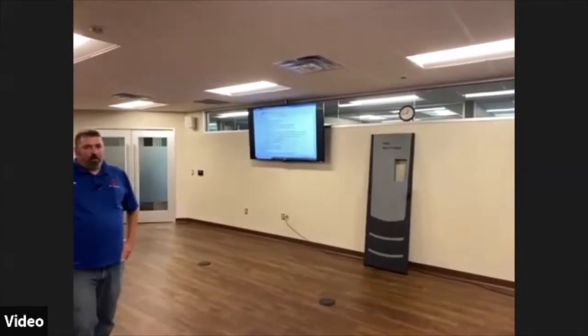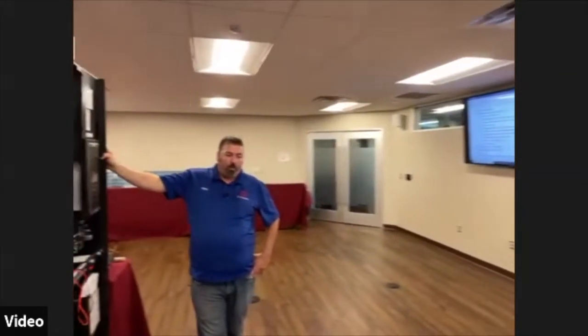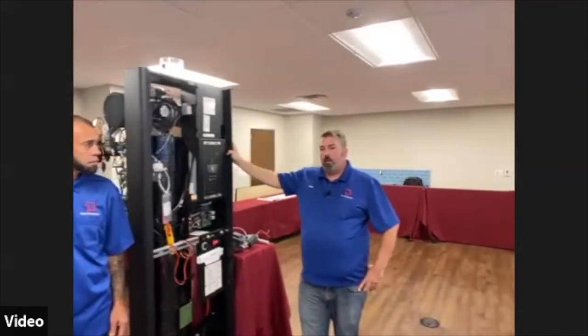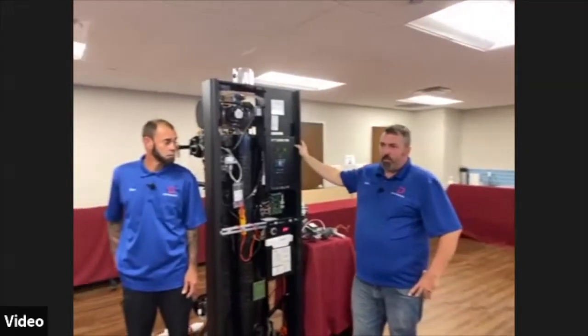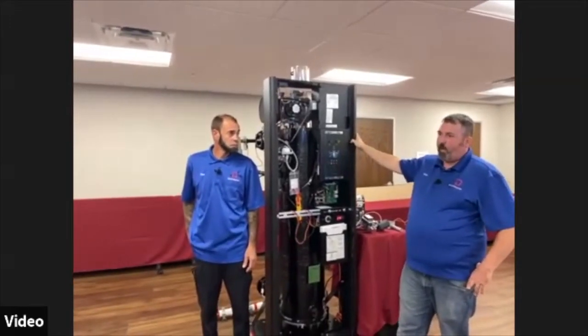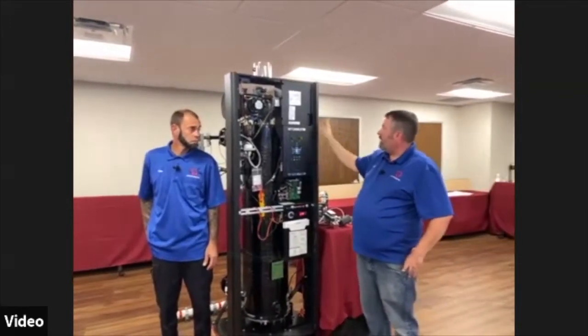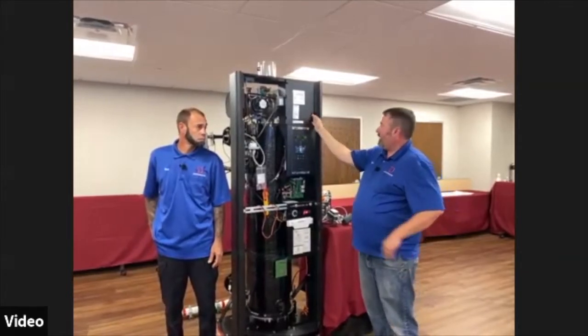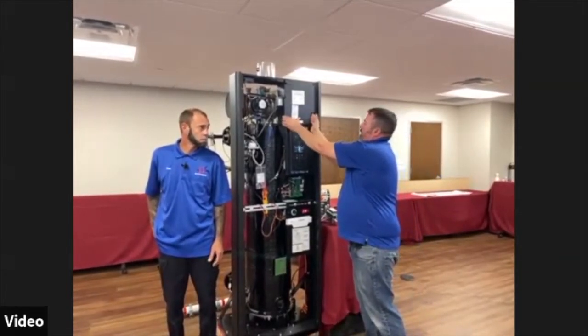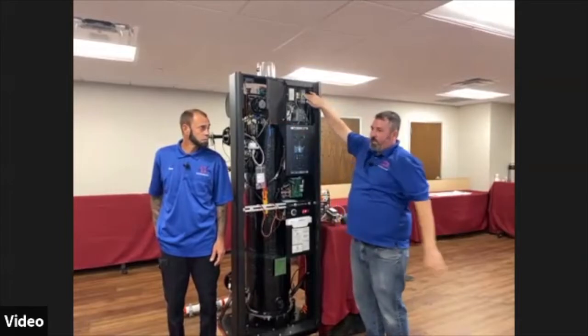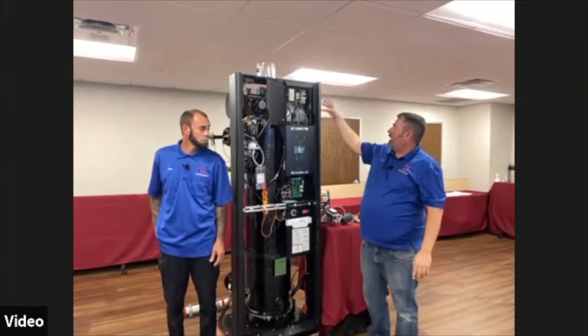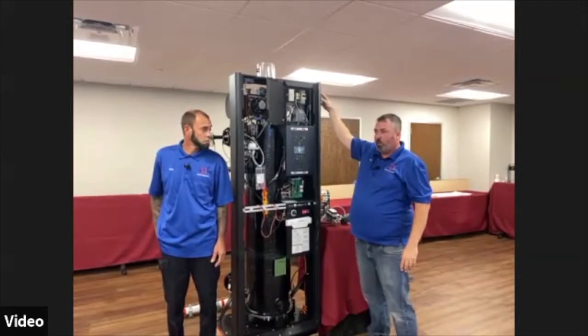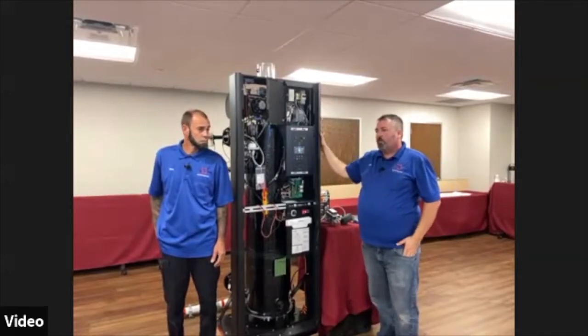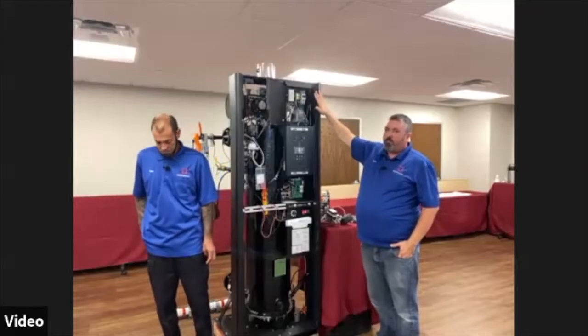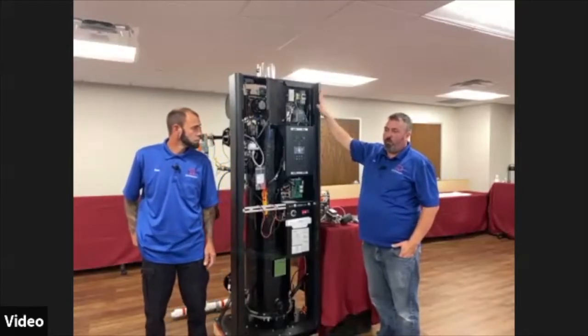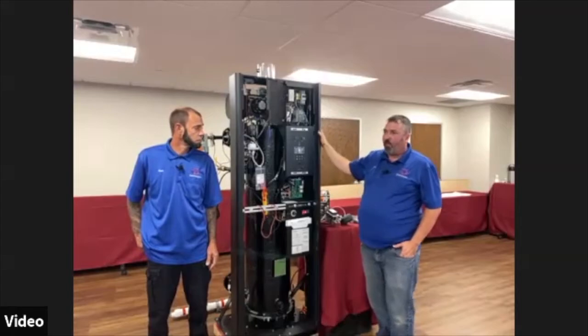Well, I know in Michigan, it will not work for CSD1. For CSD1 standards, you have to have a lockable disconnect outside of the unit within arm's reach. So since this is inside the unit, it will not pass for CSD1. And this breaker is not lockable. Most contractors mount a lockable disconnect to the boiler or on the wall behind it. So it's more of a service switch, I guess I would call it. Power the boiler down. But you still want to lock out, tag out at another source.